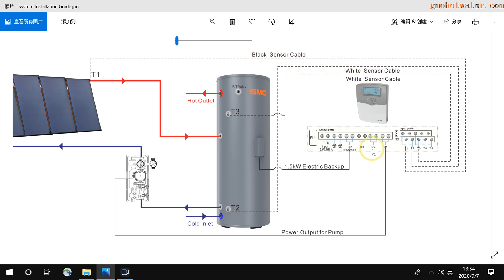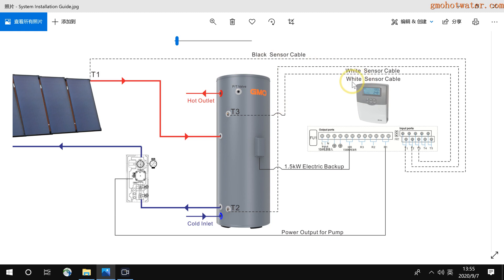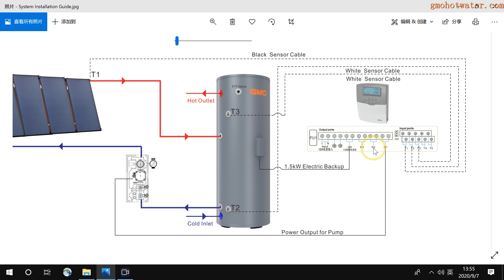And there are R2 and T4. For example, this is a very advanced function. Like if you have a lot of points to use hot water, you want the hot water pipe with hot water all the time. Then we can use an extra sensor to detect the hot water pipe temperature. But in the box of the controller, we only give you three sensors. So if you need an extra sensor, you need to buy from the supplier. To detect the temperature, you need to have an extra pump connected to R2.